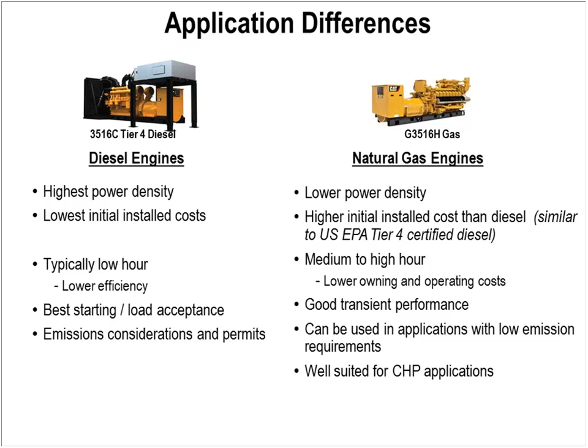The diesel engines historically have had the best starting and load acceptance. They've been at the NFPA 110 levels, 10 seconds starting, and able to pick up block loads very effectively. The gas engines now are being taught, if you will, how to do that. So we have gas engines that will be coming out in that 1,000 kW range here in the first part of the year that will be capable of being fully started and able to pick up block loads within 6.5 seconds, just like their diesel counterparts do, and to be able to do the block loads at pretty high load levels. Emissions, again, are one of the considerations that a lot of people have been looking at for these applications, and the gas engines tend to do pretty well on the emission side.